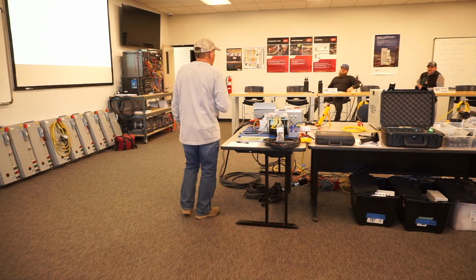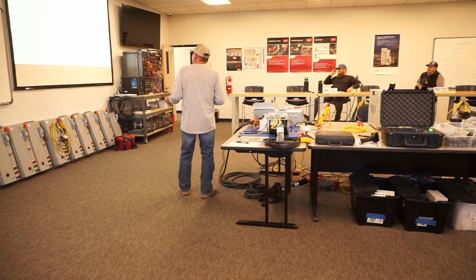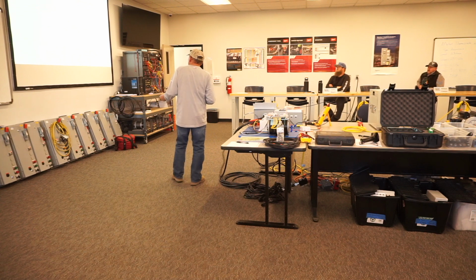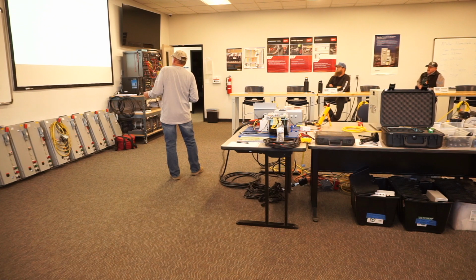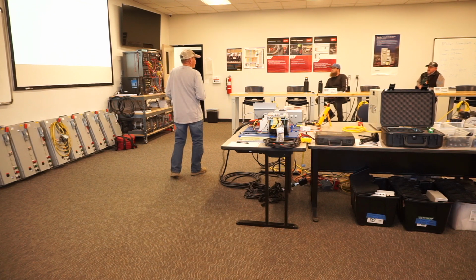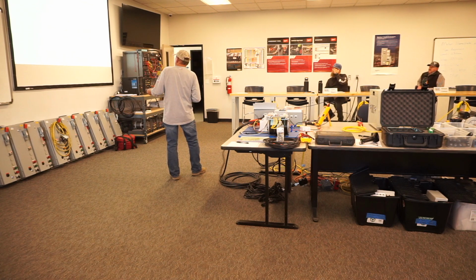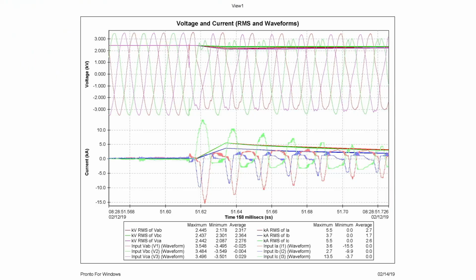Well, I had my meter on, so I downloaded the data. So what you're looking at here is, now this is kilovolts. So there's 2,500 volts, 2.4 kilovolts, right? So that's the main power. And the amps is on the different phases, and this is in milliseconds. So one cycle is 16 milliseconds. So this particular chart's running 160 milliseconds from here to here. So that arc flash happened right in here. And that's probably 8 milliseconds right there because of the half a cycle. And it generated so much energy, it was incredible.